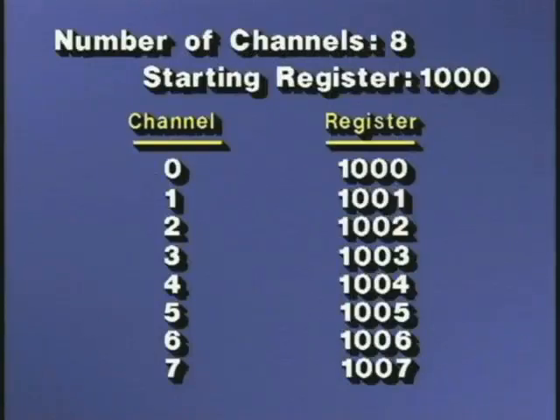If 8 channels are used and the destination register starts at 1000, then the processor will store the analog counts for each channel in registers 1000 through 1007 octal. That is, of course, if the PLC we are using has the octal numbering system. You have to bear in mind that the processor takes care of the register range automatically. However, you must remember not to overlap the assigned registers with other instructions and to keep track of which register is holding which analog count value.